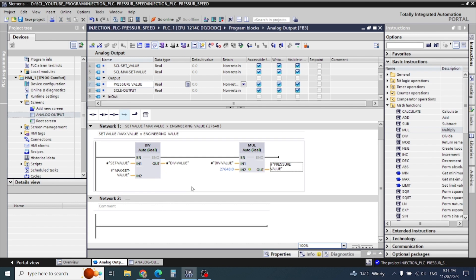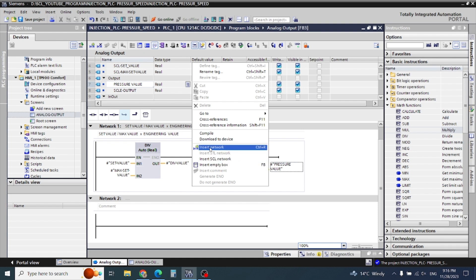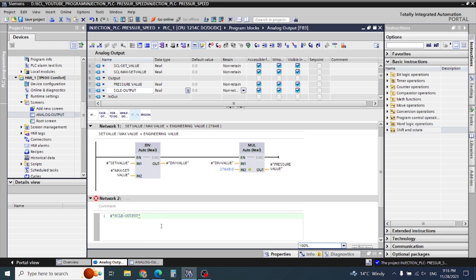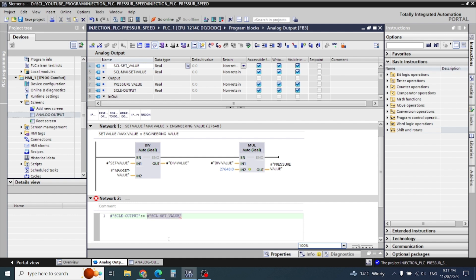If we need to enter this in SCL language, then we insert SCL. As you know in SCL, first we will write our output — same formula — then colon-equal ( := ), and I give SCL because its understanding is easy. First, small bracket: set value divided by maximum value, then close this bracket, multiply by our engineering value.